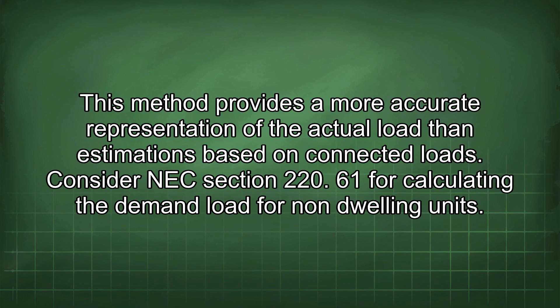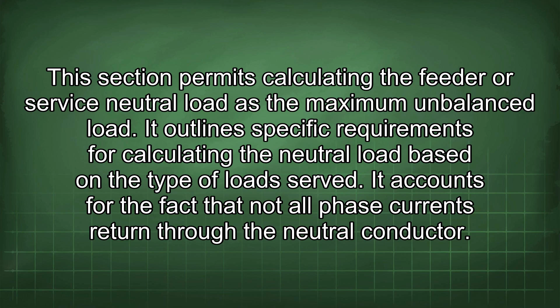Consider NEC Section 220.61(C)(1) for calculating the demand load for non-dwelling units. This section permits calculating the feeder or service neutral load as the maximum unbalanced load. It outlines specific requirements for calculating the neutral load based on the type of loads served. It accounts for the fact that not all phase currents return through the neutral conductor.